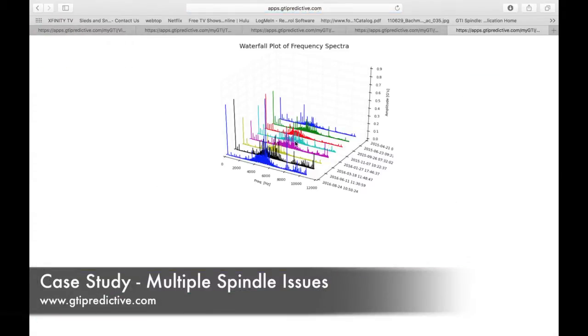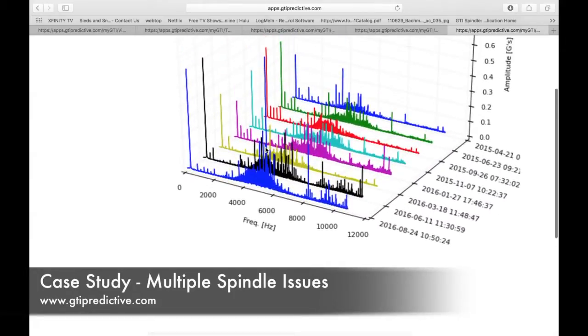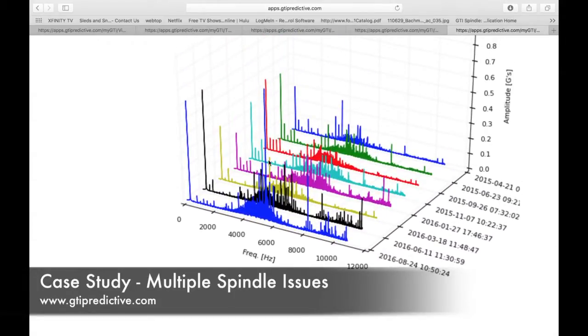Again, we see it's starting, getting a little worse, and then here at the last reading that was taken, we've got a high peak right in the center of that bearing mass that's starting to plague us along with this tall 1x running speed that is becoming a problem.